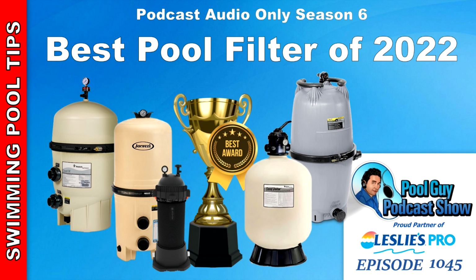The only drawback with the 4000 series filter is that the top of the tank is pretty heavy because it separates in the middle, and then you have to take the tank out. There are no handles on there, and it could be heavy for some people. The other problem with the 4000 series, not really a problem, it's just the location of the backwash valve. It's the handle on the bottom of the filter, and you have to make sure that it's installed so you can properly reach it and push it and move it.